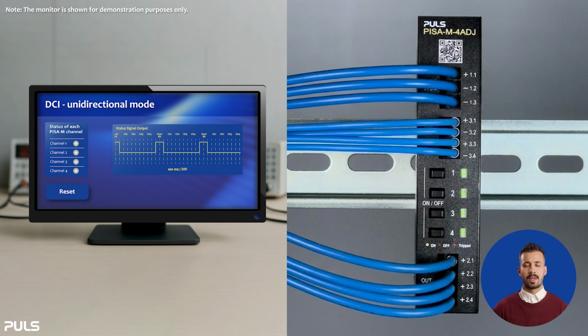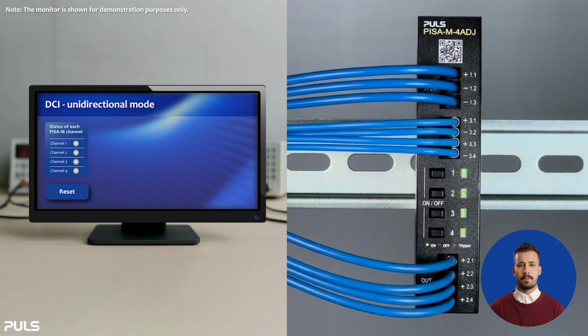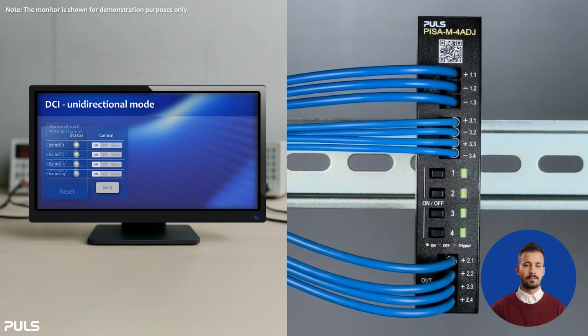Finally, let's look at bidirectional DCI mode. Here, we still see the status of each individual channel on the left side, but now we also have additional control functions for each channel. This means each channel can be controlled individually. For every channel, we can select on, off, or reset. These commands are not sent immediately one by one. Instead, the selected commands are prepared first and then transmitted together when we press send.